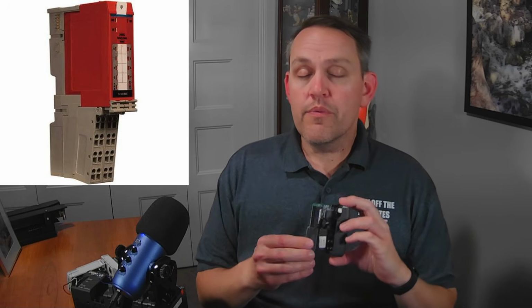But in the processor, the actual internal chips that do the processing and hold the program, there's 3 of them in there. The processor is running 3 different programs all at the same time. They're safetied in. The processor is able to have things like safety signatures on the program, to where the processor now knows if anybody has messed with the program at all. You can't sign into them, they're locked, they need a special code to unlock them. So the processor has A, B, and C essentially on it, and it's able to run the same program 3 different times. It has its own internal and external watchdogs built into it already, so it knows if it has a problem.